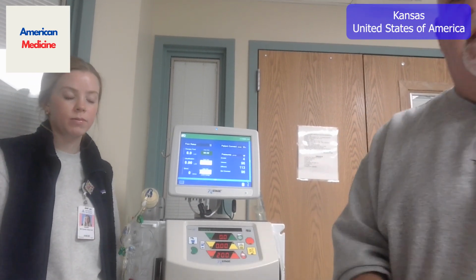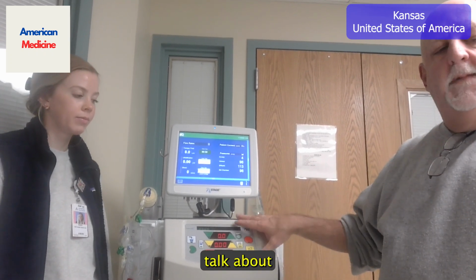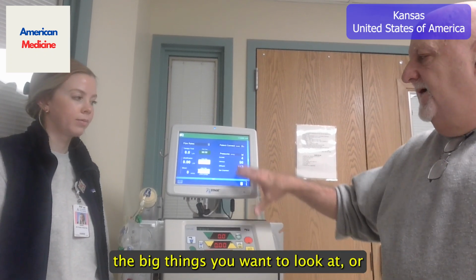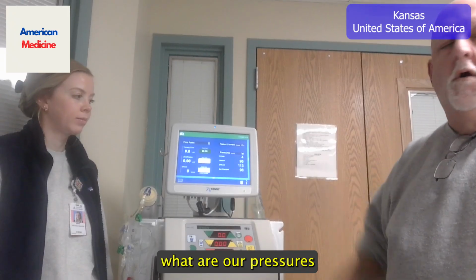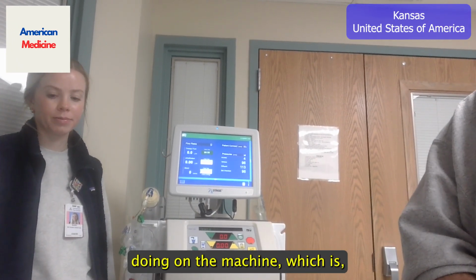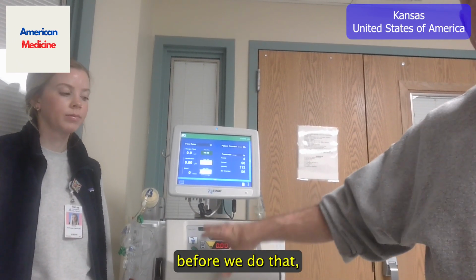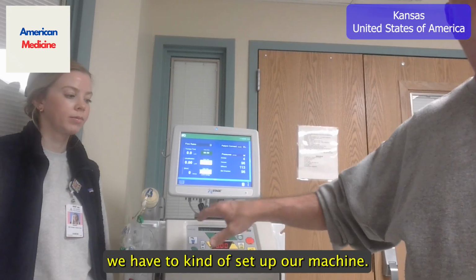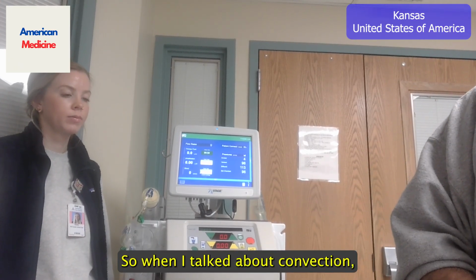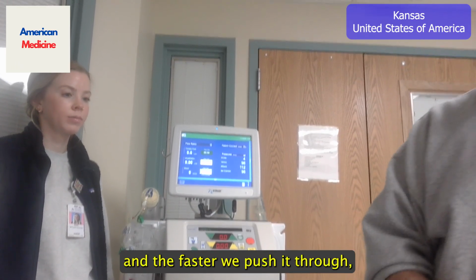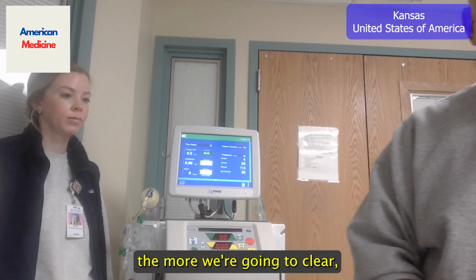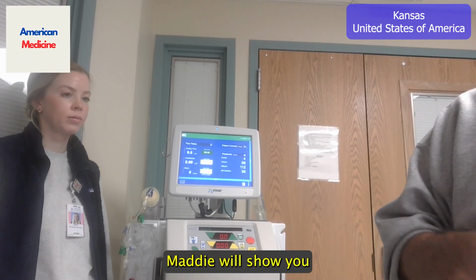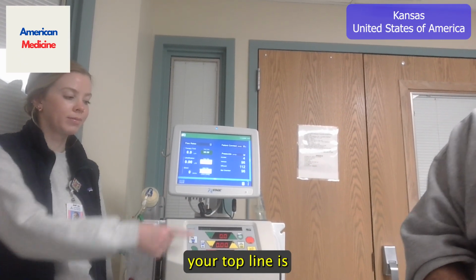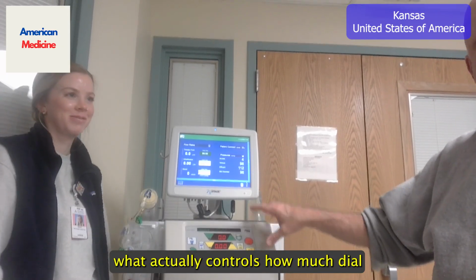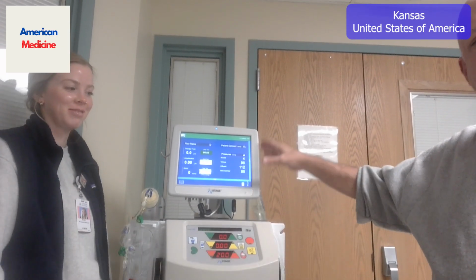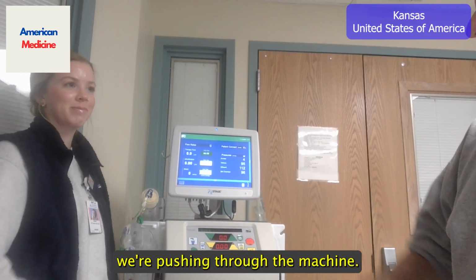When we talk about different things, the big things you want to look at are what our pressures are doing on the machine. Before we do that, we have to kind of set up our machine. When I talked about convection, the faster we push it through, the more we're going to clear. Maddie will show you: your top line is what actually controls how much dialysate we're pushing through the machine.